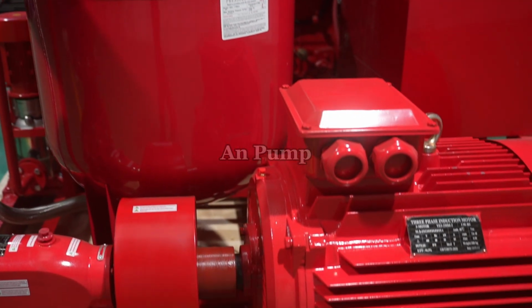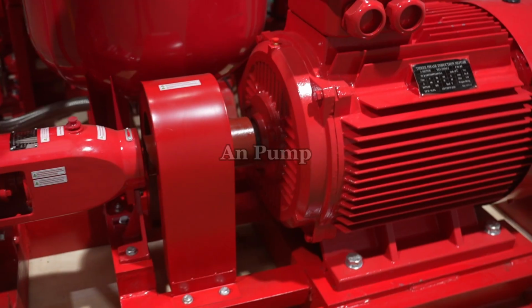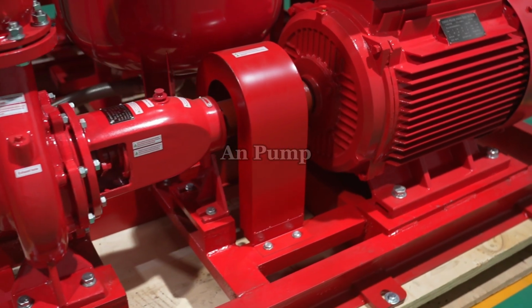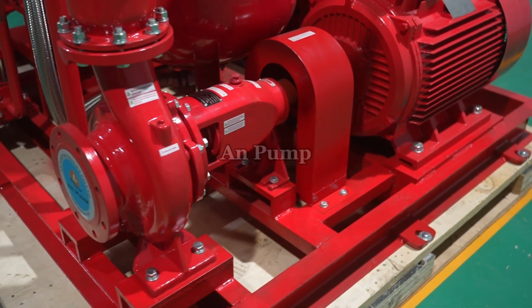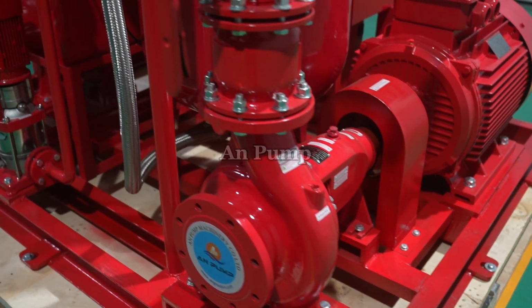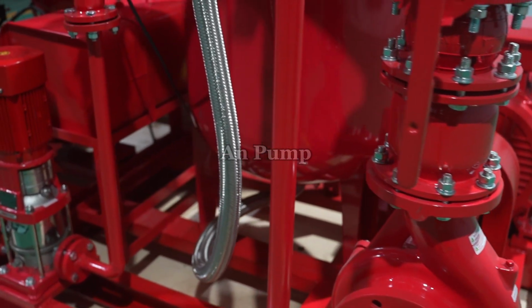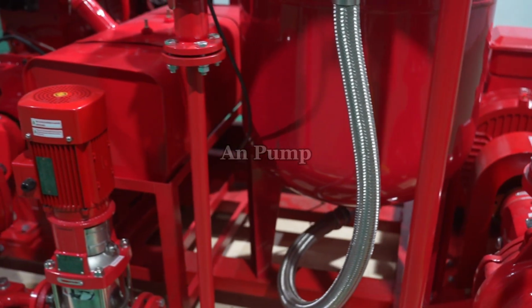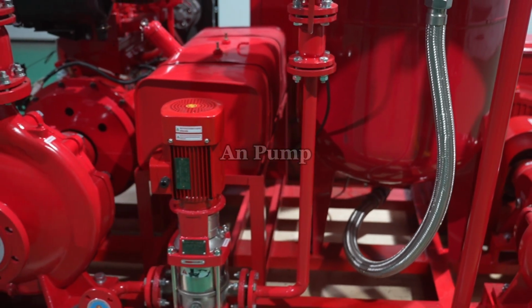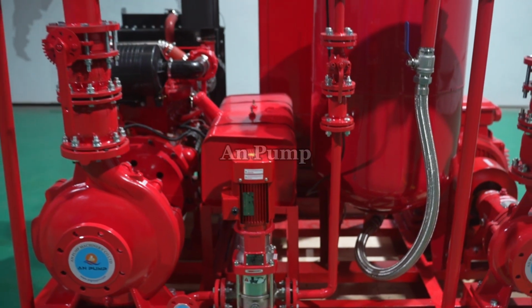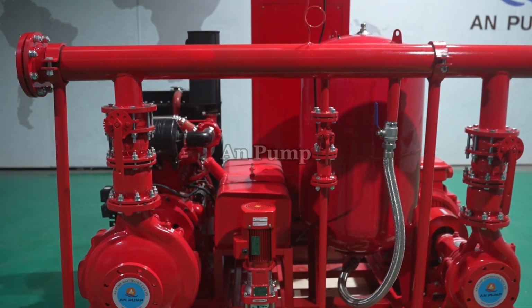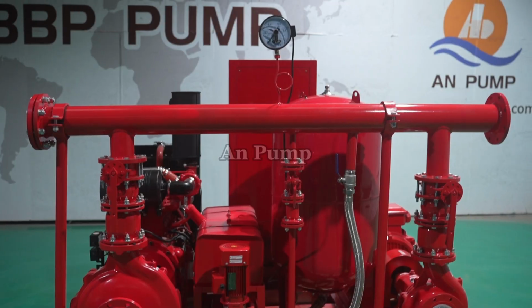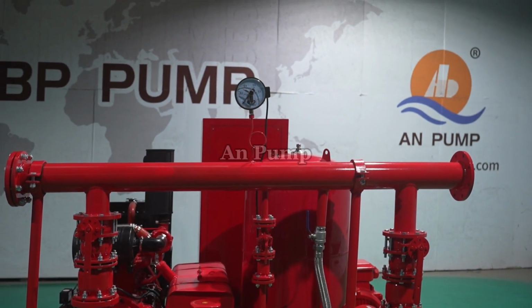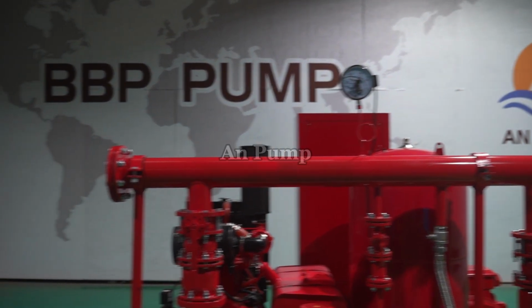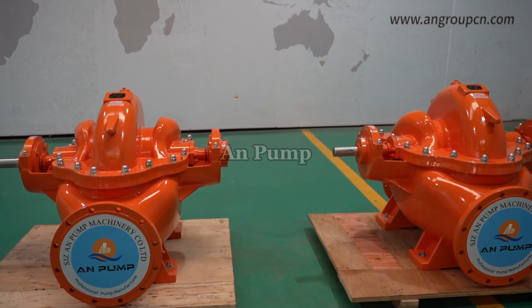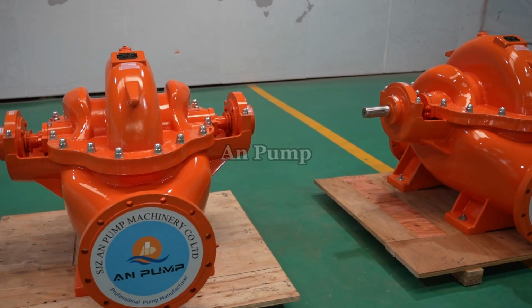End suction pumps are ideal for HVAC water circulation, light chemical transfer, agricultural irrigation, general water supply, and fire protection systems. They typically handle flow rates up to about 5,000 gallons per minute and heads up to around 500 feet. The main limitation is that they can't generate very high pressure. They're also not well suited for thick fluids or liquids with a lot of solids, because efficiency drops and wear becomes a problem.